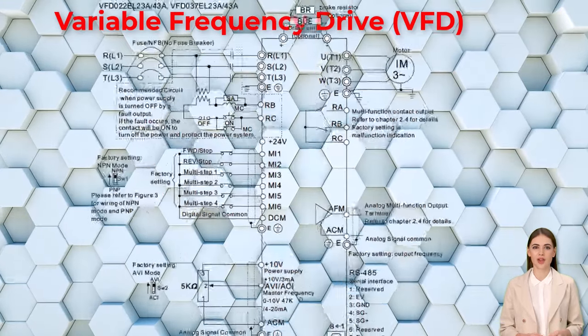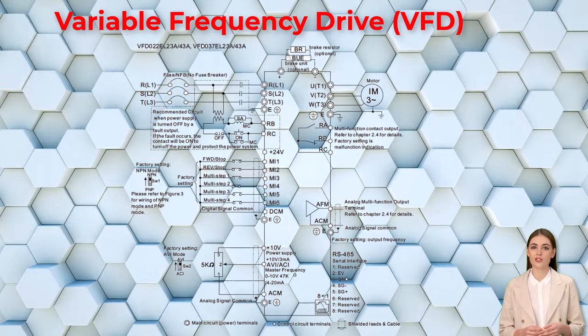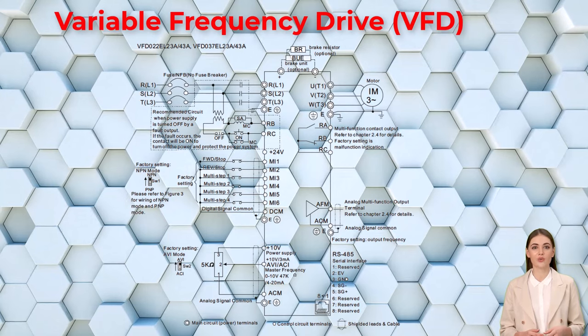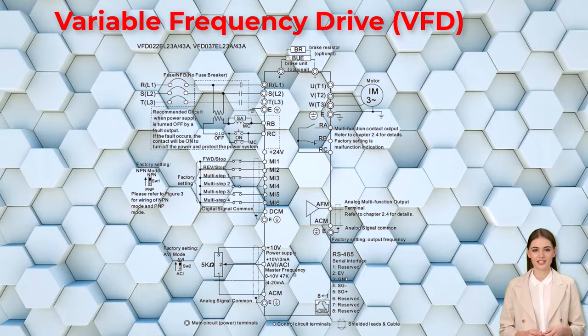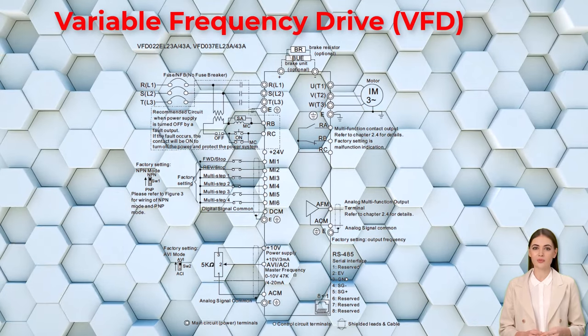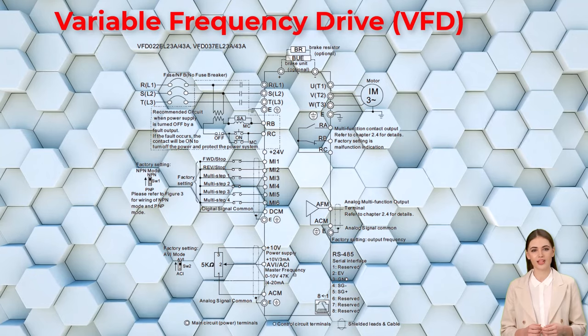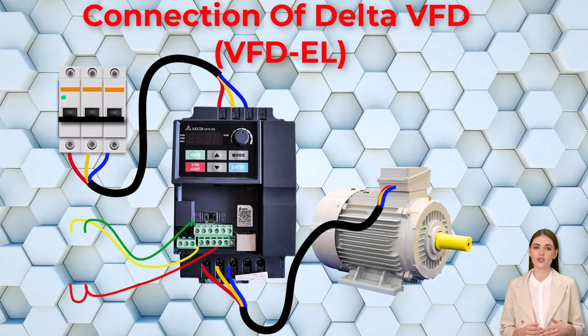Let's look at the power and control connections of a VFD with an induction motor. First, check the manufacturer's catalog carefully — here we are using the Delta VFD-EL. For power connections, three-phase supply is applied to terminals R, S, and T. The output terminals U, V, and W are connected to the induction motor. Connect the VFD to the induction motor following these instructions.